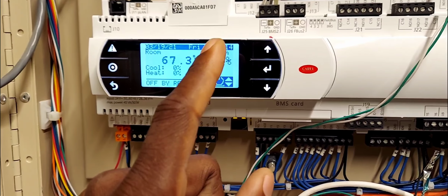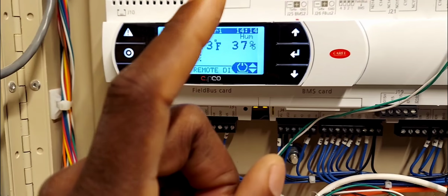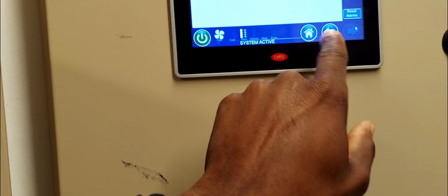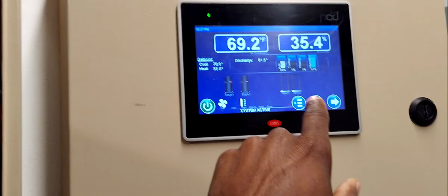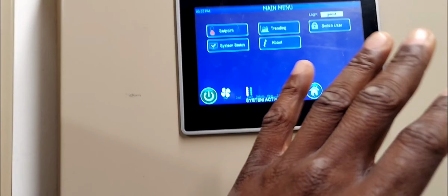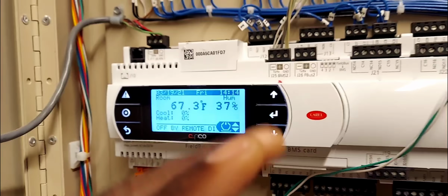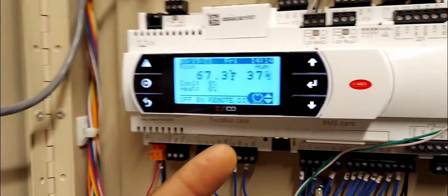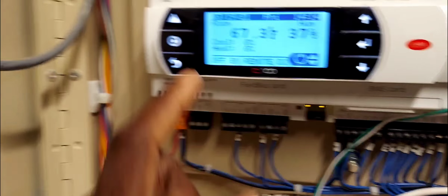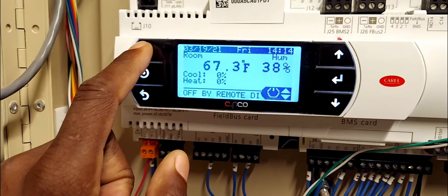When I was here last, this unit had a, what was it, a high pressure alarm. This one was fine, okay? This one was running fine. There was no alarms on that. However, the customer was saying that their issue was that they were getting low humidity alarms. Nonetheless, let's go into the logs.